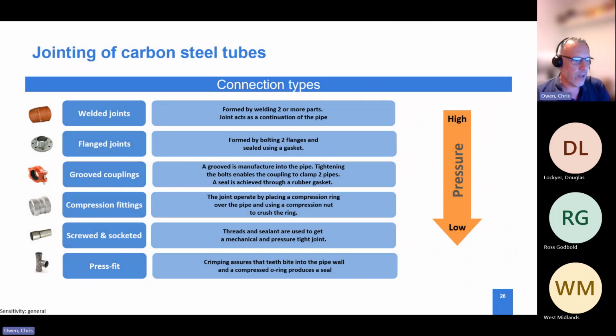Just referring to jointing, it surprises me that people don't really understand the effects jointing has on the pressure integrity of a system. We'll get asked time and again, what's the pressure rating of your pipework? That's great, pipework can do up to 100 bar depending on the grade of steel and wall thickness. However, it's all irrelevant, because the weakest link is the joint. Unless you're welding the tubes directly together, you're going to see exactly the same pressure integrity issue.